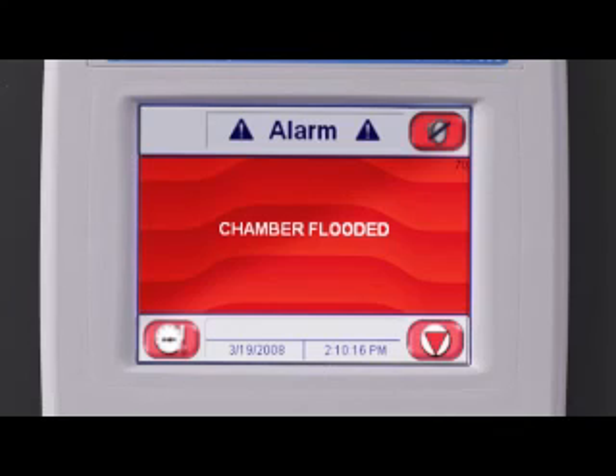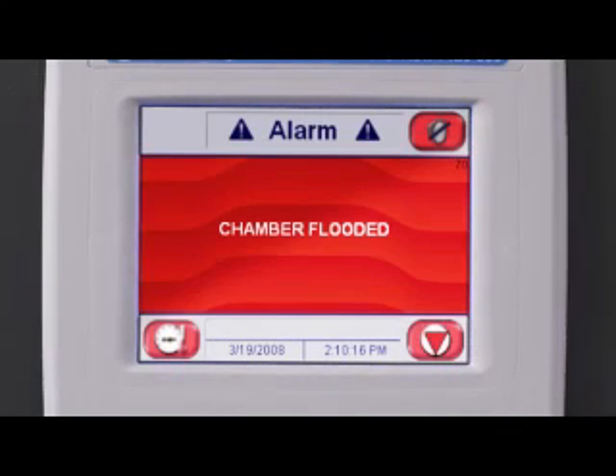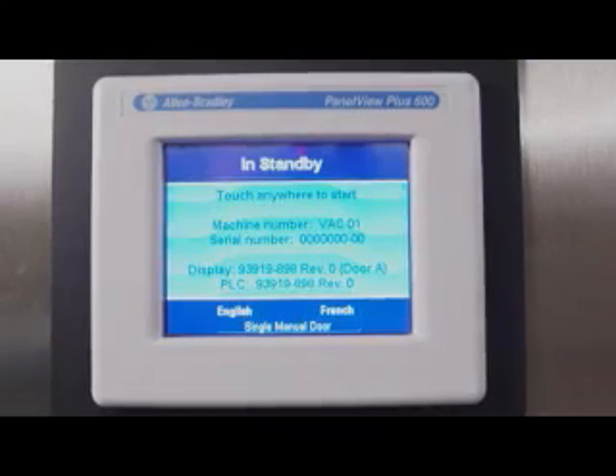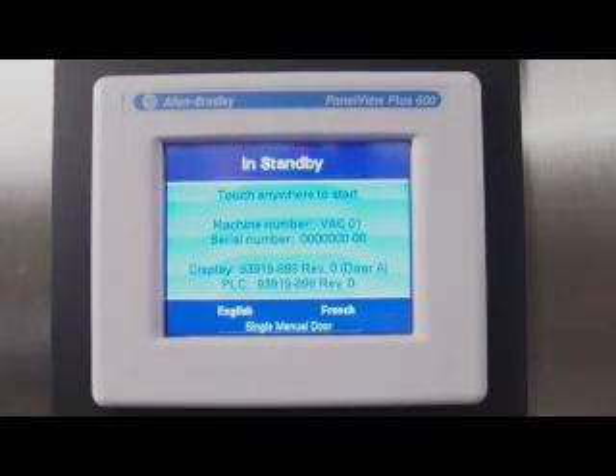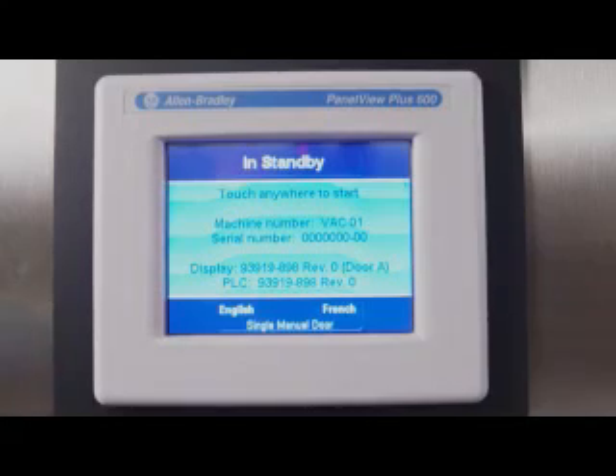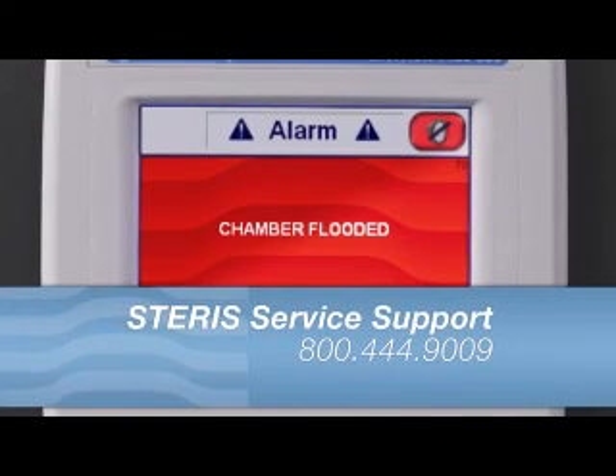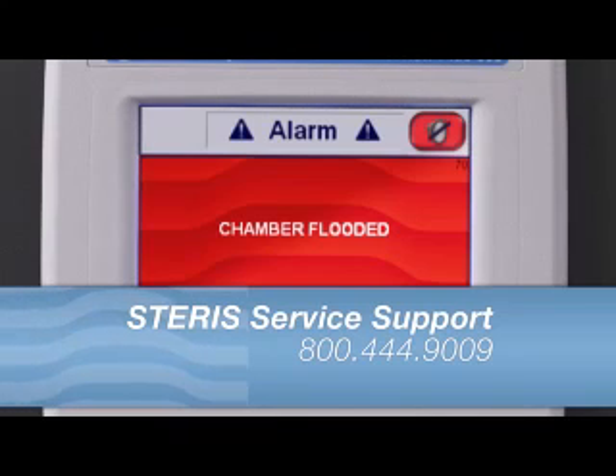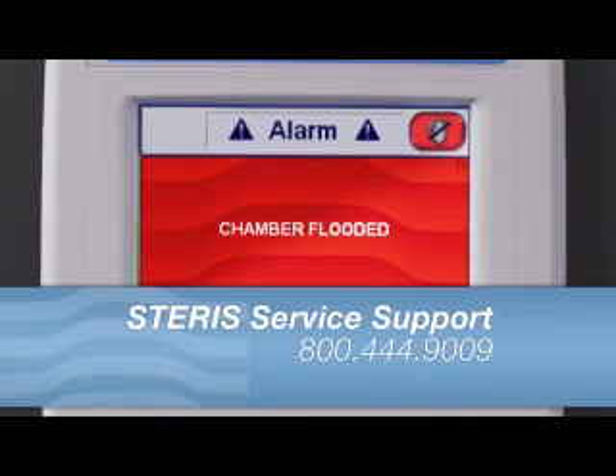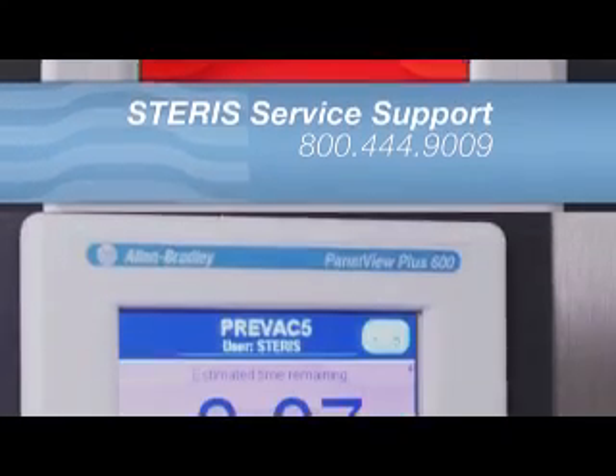For those alarms that are a result of a malfunction or potentially dangerous condition, such as a flooded chamber, the cycle will abort. When a cycle aborts for an alarm, the sterilizer stops and returns to a safe standby state. Once the sterilizer has returned to a standby state, the door seal deactivates and the control returns to standby mode. Contact your STERIS service representative or other service technician to report this issue, and do not operate the sterilizer further.